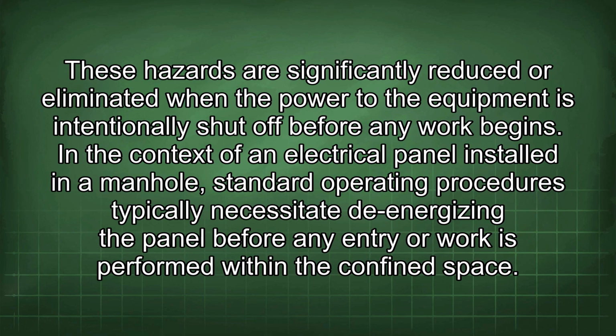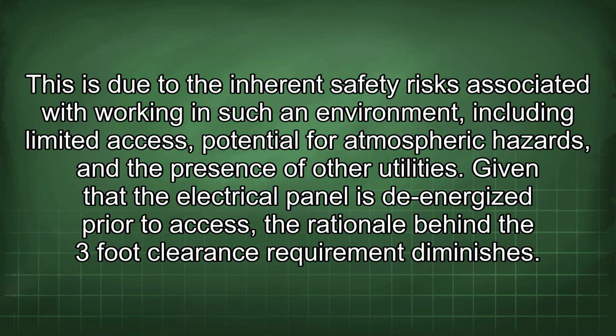These hazards are significantly reduced or eliminated when the power to the equipment is intentionally shut off before any work begins. In the context of an electrical panel installed in a manhole, standard operating procedures typically necessitate de-energizing the panel before any entry or work is performed within the confined space. This is due to the inherent safety risks associated with working in such an environment, including limited access, potential for atmospheric hazards, and the presence of other utilities.